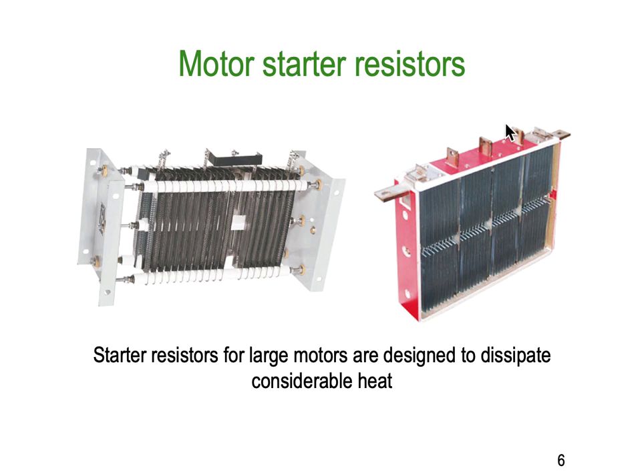Here are some pictures of those motor resistors. You can see they're quite large, with low resistance values but large wattages, because they have to dissipate a fair amount of energy. They're connected in stages with tappings — tapping one, tapping two, tapping three, tapping four — giving four groups of resistors. They often have to be mounted somewhere well ventilated so the heat produced at start can be dispersed quickly.